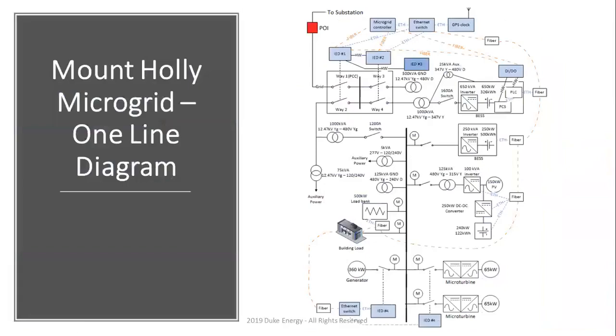For those of you who wanted to see how this whole thing looks on the electrical and communications line diagram, you can see over here, there's a substation that comes to the point of interconnection, which is the recloser where everything goes over to the distribution control center. And then in order to separate and create a microgrid, it's a 4-way switchgear that you see over here. It's way one of the 4-way switchgear that we open.